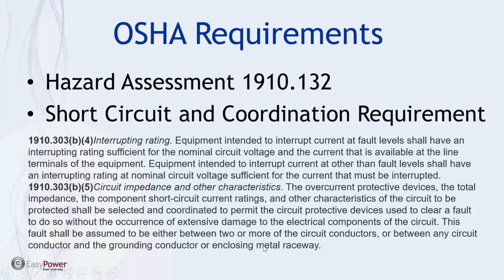This fault shall be assumed to be either between two or more circuit conductors, phase to phase, or between any circuit conductor and the grounding conductor or enclosed metal raceway. So the box, whatever's grounded, and that phase to ground would be a ground fault. So this is pretty clear that a short circuit study and a coordination study is required.